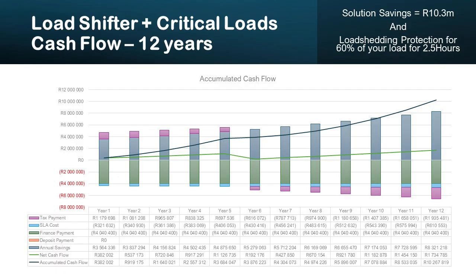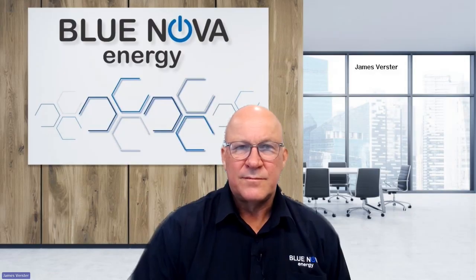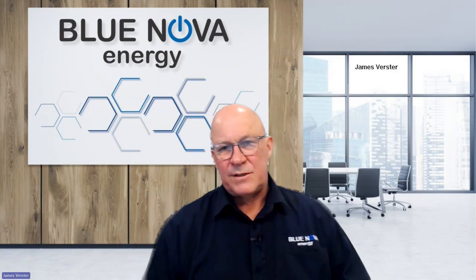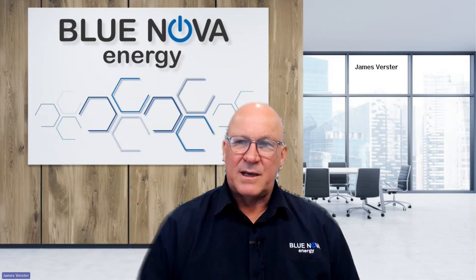That's a significant number, having considered that the customer does not take out a single cent to activate this whole project. So a little busy slide here, just showing how we get to the 10.3 odd million rands worth of saving. Just so by the way, the system is sized in such a way that in this specific case, 60% of the load still has load shedding protection. So all the engineering labs and offices and those areas which are very sensitive to load interruptions during load shedding, because before generators or something like that starts up, we want seamless backup. 60% of the loads can get seamless backup.